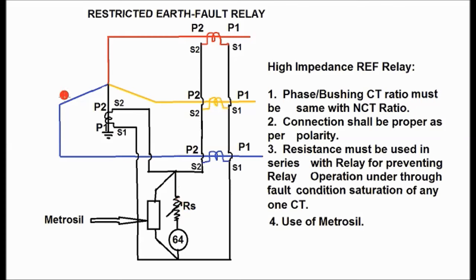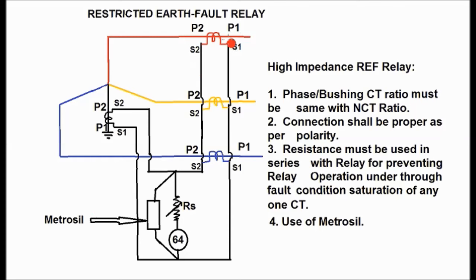First I will discuss about the advantages of the high impedance type and when we cannot actually use the high impedance type restricted earth fault relay. In this diagram, for the star side of the winding, the restricted earth fault high impedance type relay connection has been shown. The formation is simple — all the phase CTs or bushing CTs, whichever is taken, form the restricted earth fault relay.